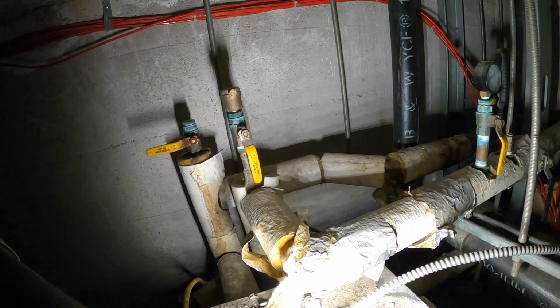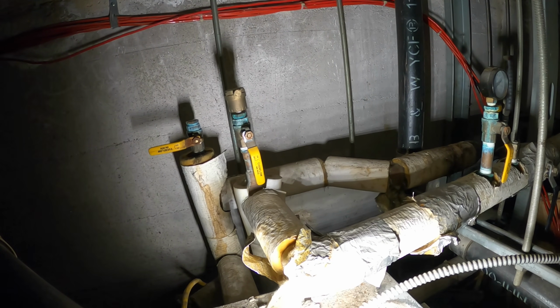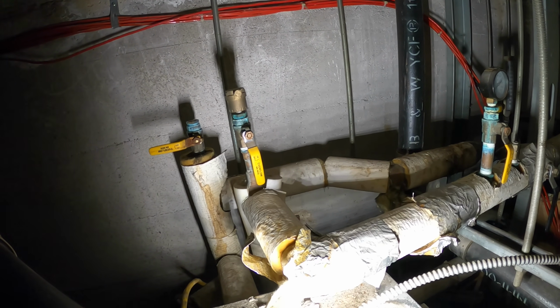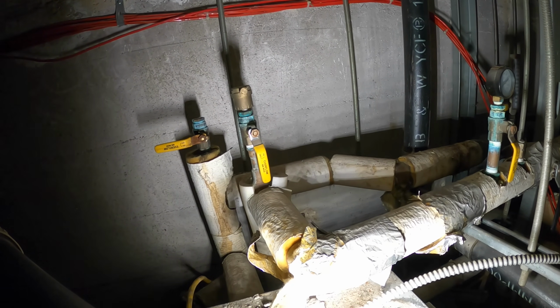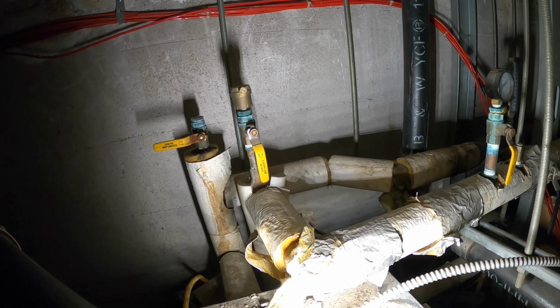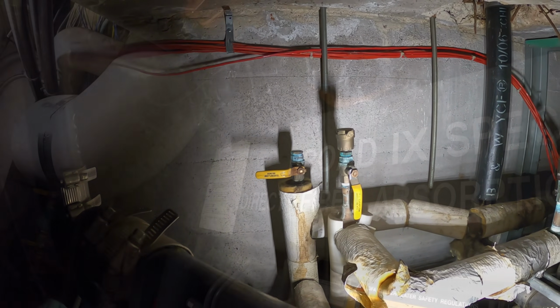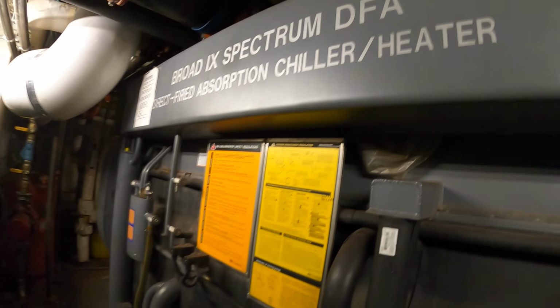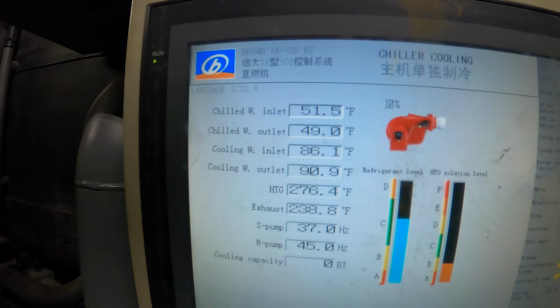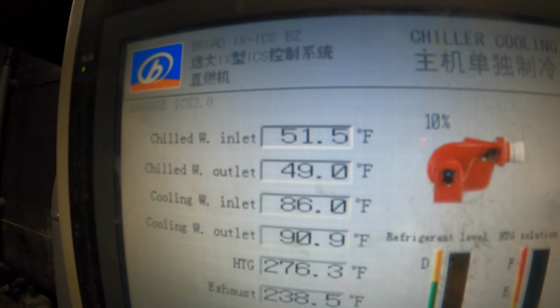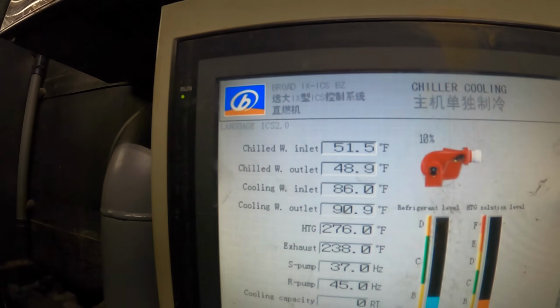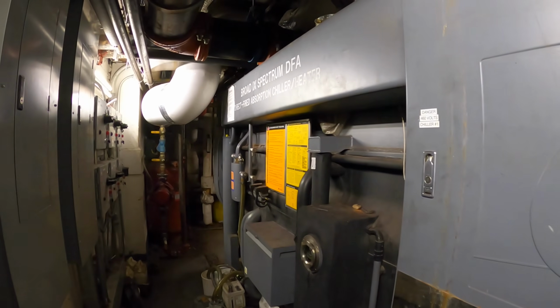Still the same. Either the chiller is not on, or somehow we're not moving water because we got air in the pipes, or possibly there could be a strainer here that's clogged as well. The fan is running. I saw the belt was kind of loose, but if that coil was cold, man, you'd get cooling. We gotta investigate. All right. We look here. Chilled water inlet 51.5, chilled water outlet 48.9. Chiller is operating. Either a valve is closed somewhere, the strainer's clogged, or we're airbound and we're just not moving water.